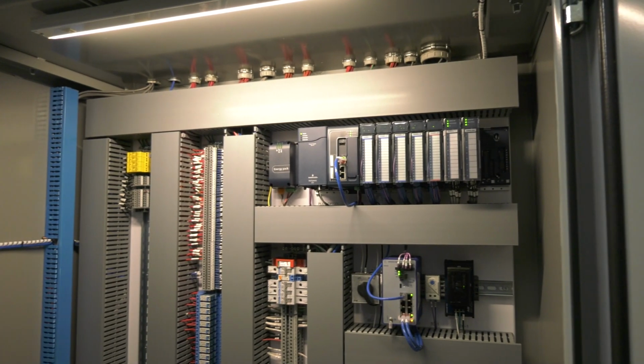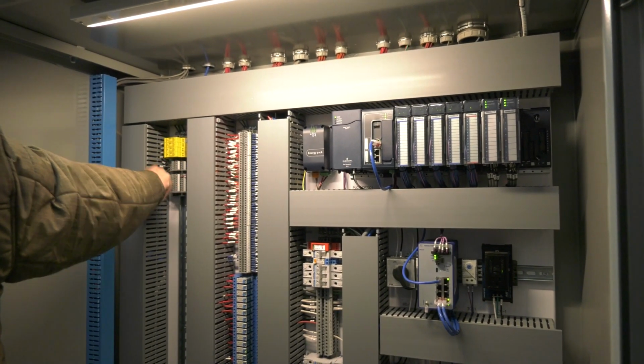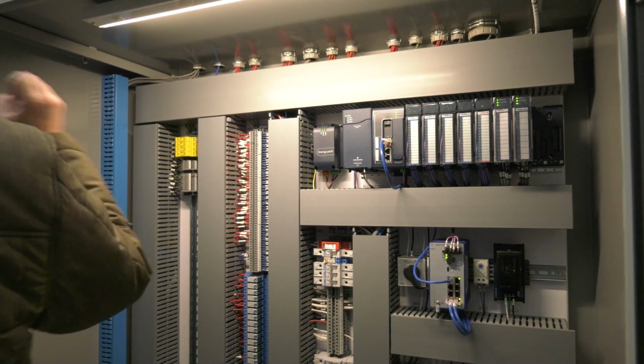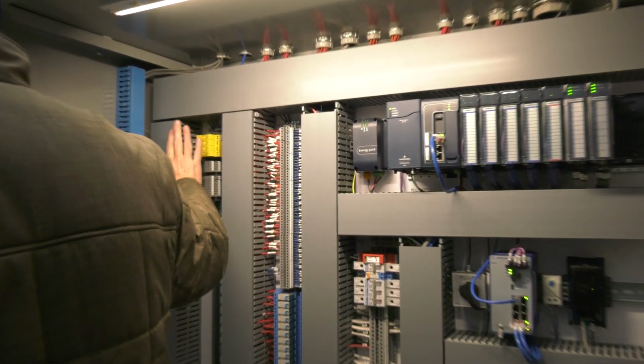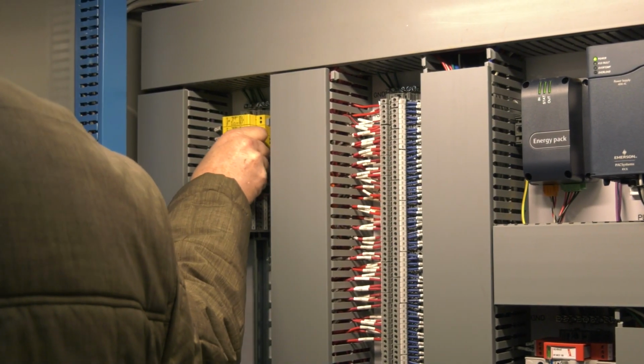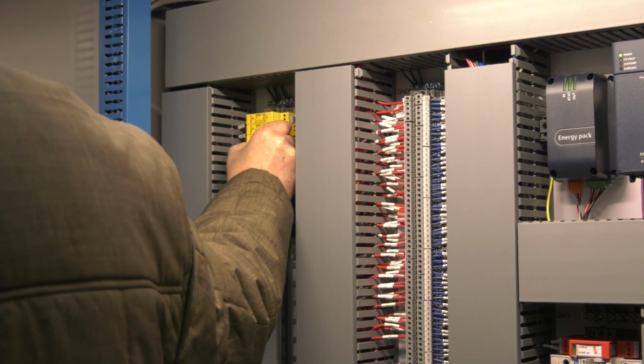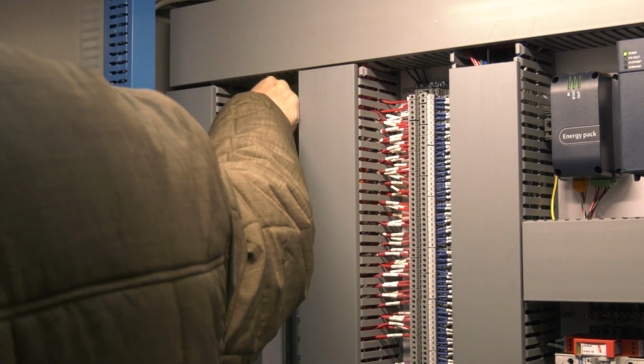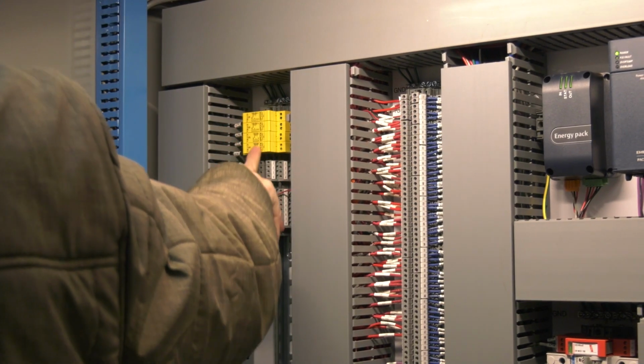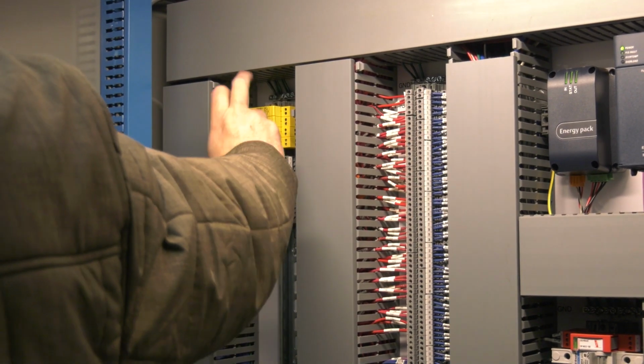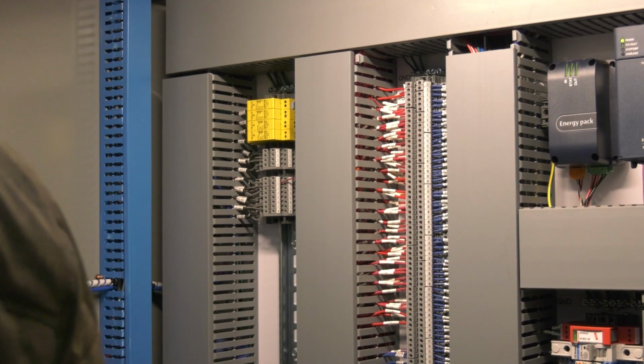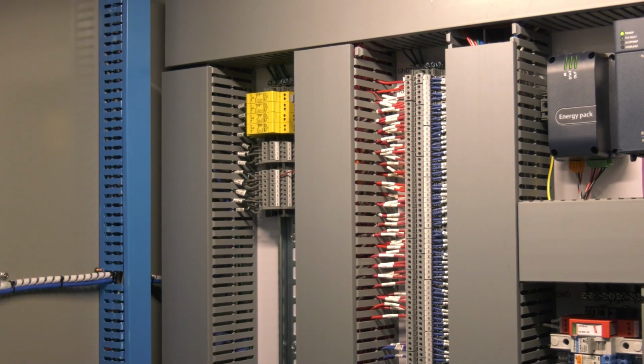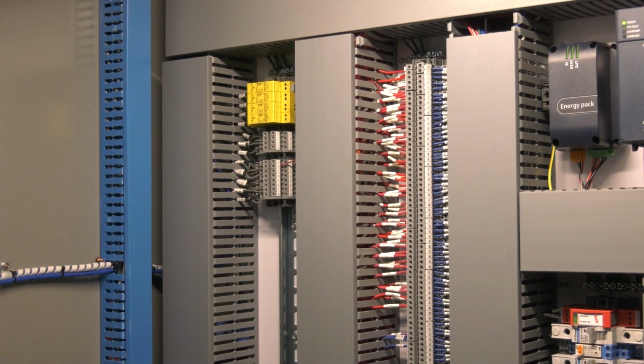Yeah. And these are a little different surge suppressors here. These are for your 4 to 20 analog signals. And again, these are make before break, so if you have a problem, they're really hard to get out. But these modules will pop out. If you lose an analog signal and you don't have a spare module, just pop the module out, and your analog signal will resume working. So that's just something you might want to tell the maintenance guys.